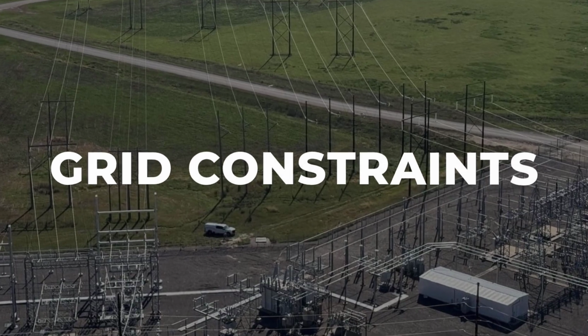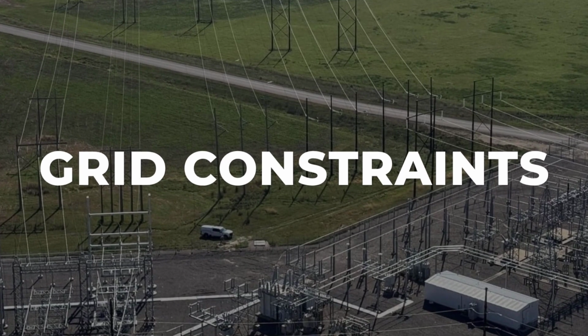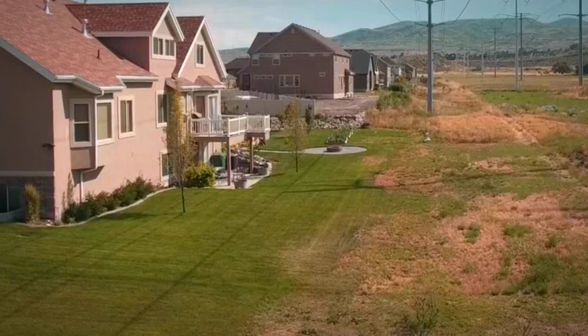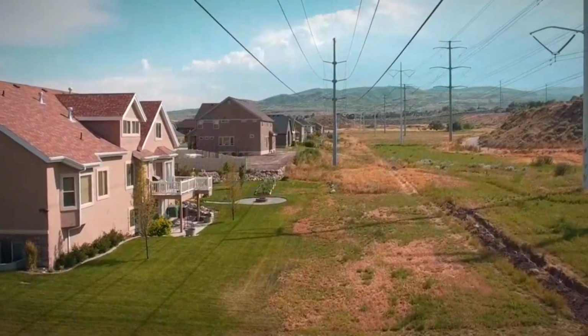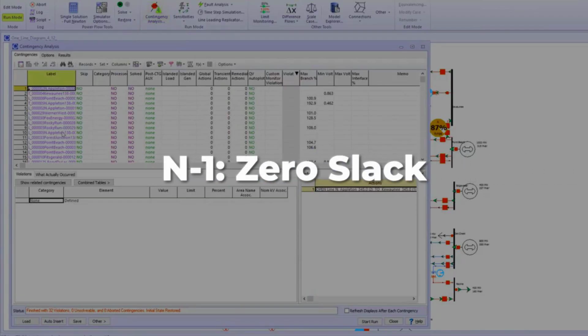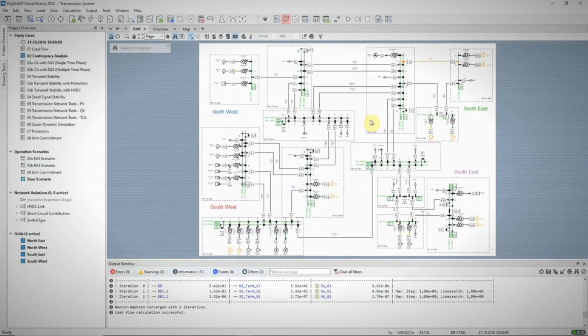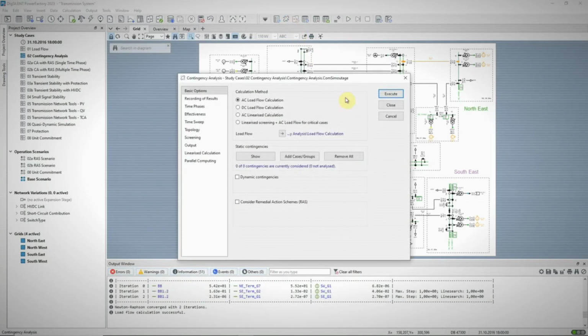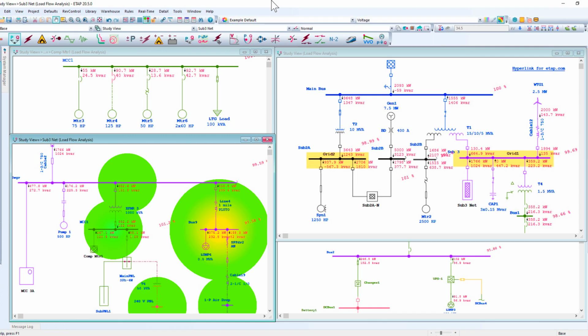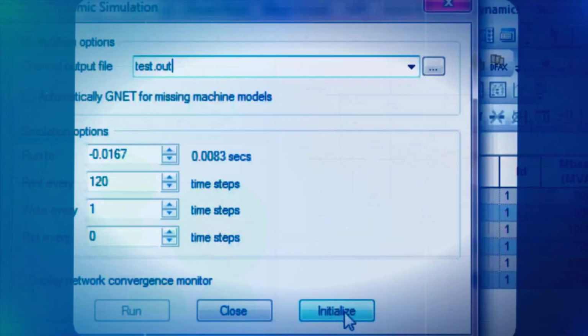Grid operators do not treat high-voltage transmission lines as isolated assets. Each corridor is a node in a tightly balanced network, governed by contingency planning rules known as N-1 and N-2. These standards require the system to withstand the unexpected loss of one, or sometimes two, major transmission elements without breaching voltage or thermal limits. The calculation is not theoretical.